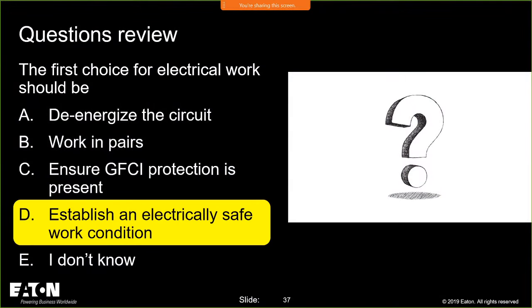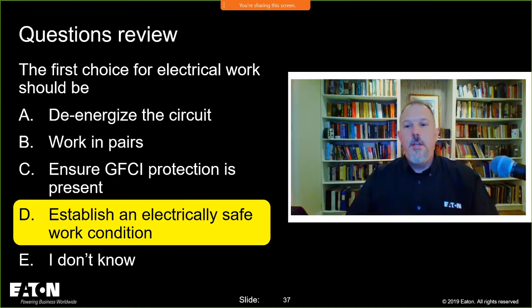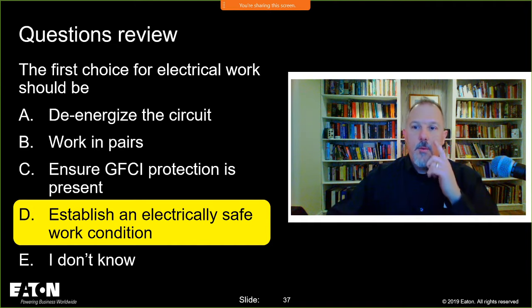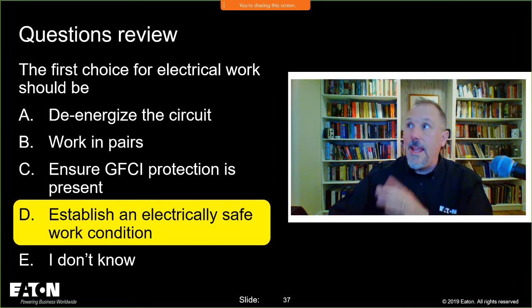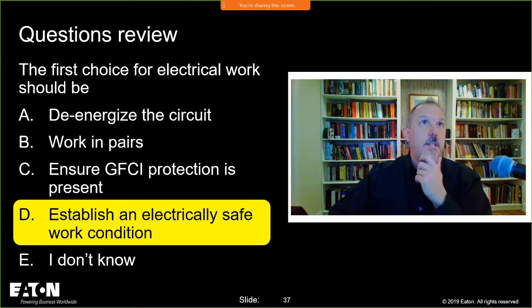All right, so that's what he did. He basically established that he charged that breaker and then he closed that breaker. Once you have that charging arm in there, you will actually close that breaker, and it's charged and ready to go. And that's what we're talking about with regard to stored energy. So the right answer to this one was establish an electrically safe working condition.